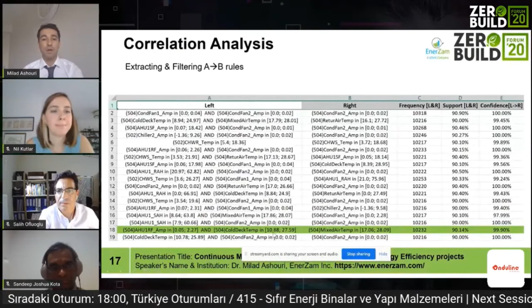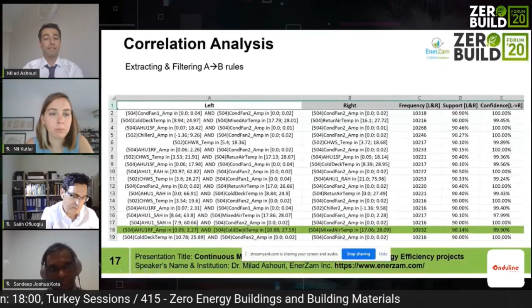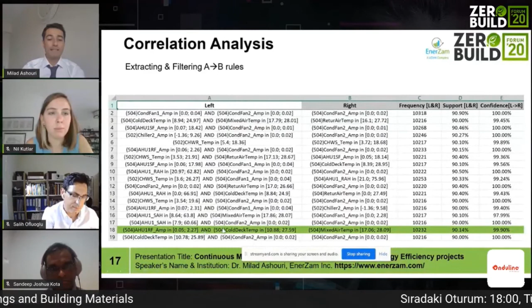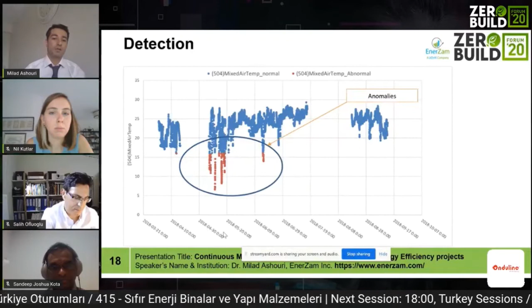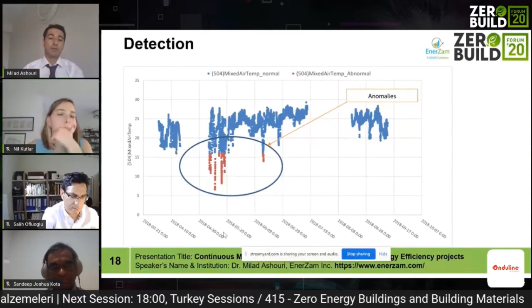For example, the air handling unit return fan, cold deck temperature, and mixed air temperature are dependent on each other. So by looking at the data, whenever this correlation is violated, we flag it. Here you see an example of detection on mixed air temperature, showing something going wrong in the boiler. We flag these and report them in a prioritized manner to the building engineer.